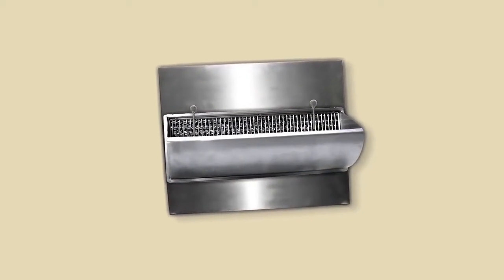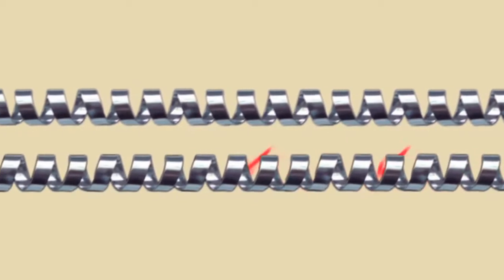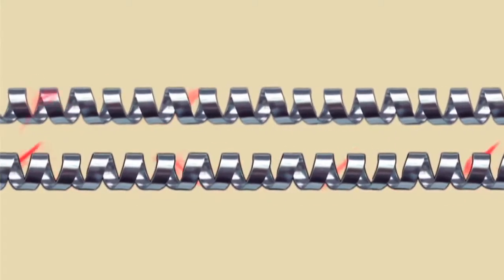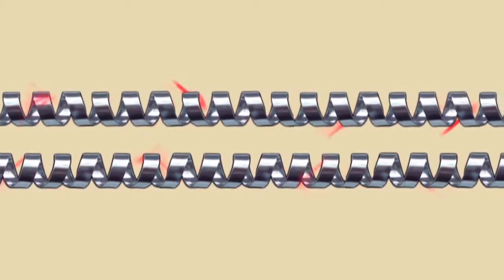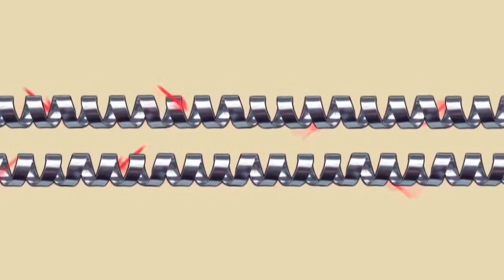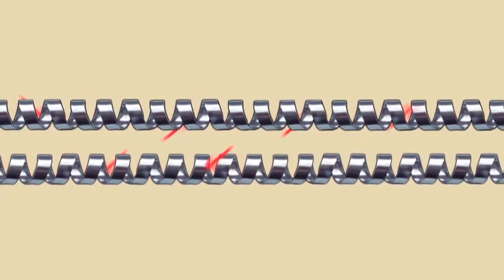The Veritech grease filters use their patented spiral curl technology to guide the airflow from the cook line through a matrix of specially designed spiral curls. The airflow has forced contact time with the spiral matrix, which forces the grease and particulates to attach and then drip into the grease collection tray.